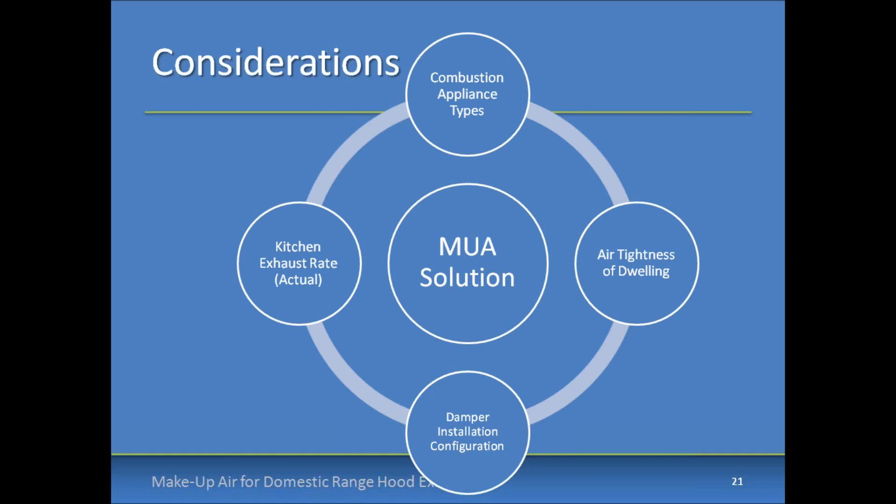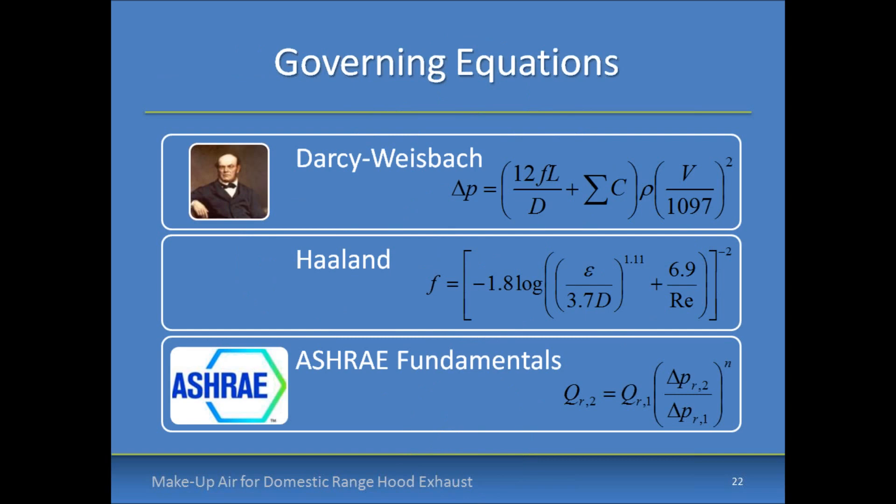Additional considerations include installation configurations and the boost available through integrating with the furnace, and the actual kitchen exhaust flow versus the nameplate rating — a fan rated at 1,000 CFM may not provide that total flow once ducting and elbows are factored in. The governing equations from Darcy-Weisbach, Haaland, and ASHRAE can get complicated, so the Broan make-up air tool uses these equations so that you don't have to. If you're an architect or engineer wanting to size ducts on your own, you can reference ASHRAE Fundamentals, but know that the basis for this tool is grounded in engineering design.